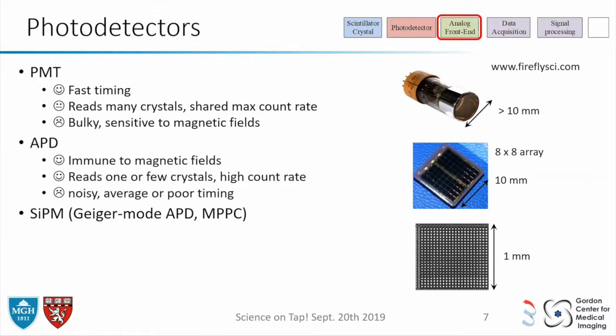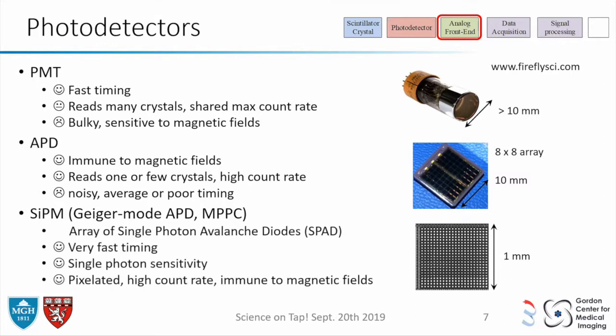That's why we moved to APDs — they're immune to magnetic fields. Each APD reads one crystal, so you can get really fast count rates. But they're noisy and timing is not so good. Lately we've been moving to SiPMs, which get the best of both worlds. They're very fast, can detect very few photons so they quantify the crystal output really well, can be made very small, have high count rates, and give overall good imaging.